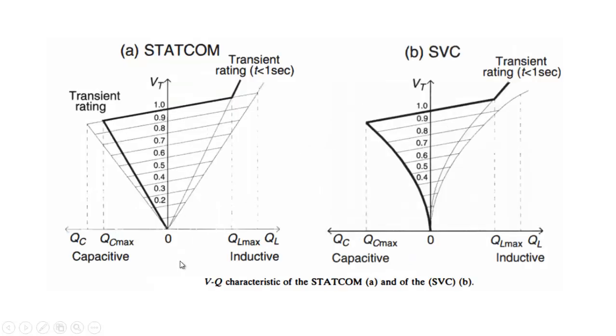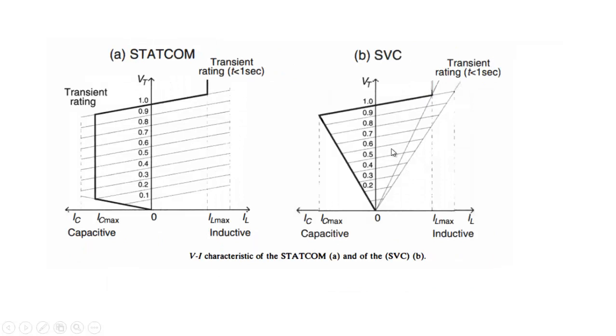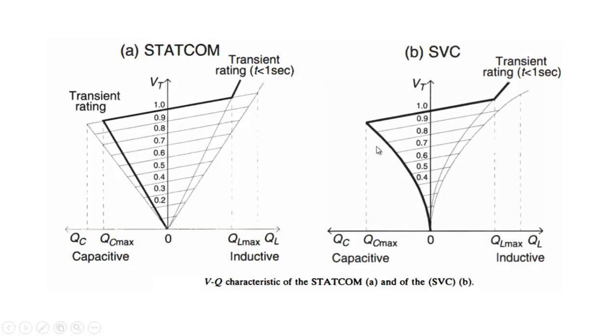For the VQ characteristics, with voltage on one axis and Q on the other: since Q equals current multiplied by voltage, as voltage decreases the reactive power also decreases because current is constant for the STATCOM. For the SVC, since the current itself depends on voltage, the reactive power depends on the square of the voltage — it equals V² divided by Xc. As voltage decreases more, there is a greater decrease in reactive power.